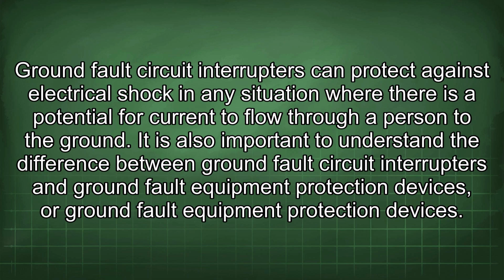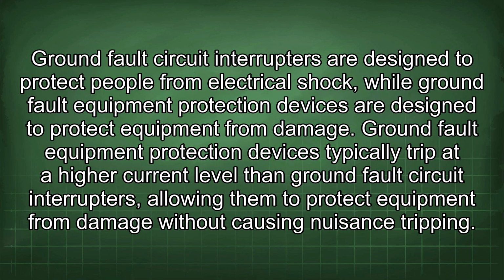It is also important to understand the difference between ground fault circuit interrupters and ground fault equipment protection devices. Ground fault circuit interrupters are designed to protect people from electrical shock, while ground fault equipment protection devices are designed to protect equipment from damage. Ground fault equipment protection devices typically trip at a higher current level than ground fault circuit interrupters, allowing them to protect equipment from damage without causing nuisance tripping.